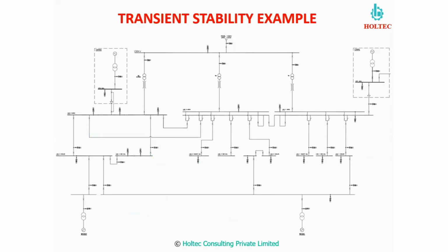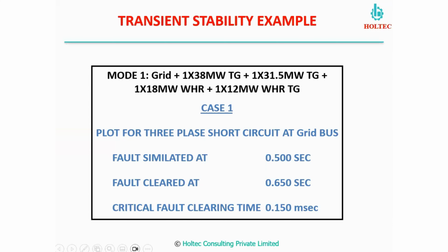This is a critical example where we have 3 grid transformers, 2 CPP and 2 WHR, so 4 plus 3, 7 sources are there. We have multiple lines connected to this distribution network, and here we created the fault: a 3-phase short circuit fault on the grid. The fault was created at 0.5 seconds and cleared at 0.65 seconds in the simulation. So the total fault clearing time is 150 milliseconds.